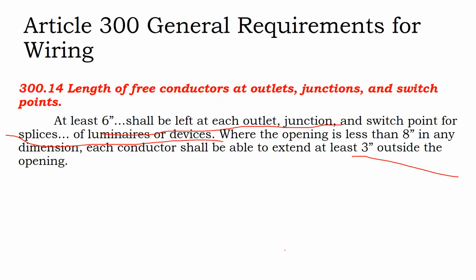I don't see any requirements in the solar industry at this point requiring a certain amount of slack in your cables, and it's a fine line between having some additional room in your cable flexibility versus installing the cables in a workmanlike manner. Generally, you don't want a lot of slack because the conduit box gets messy. So I don't see any similar requirements like when you're installing a ceiling fan or maybe a light switch. You have to leave slack so that you can pull the wires out and work inside them. I don't see any similar requirements like that in solar boxes at this time.